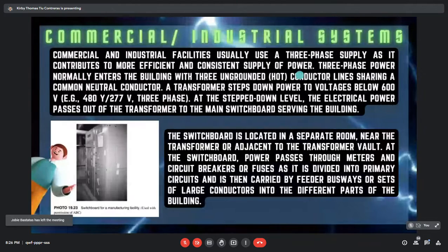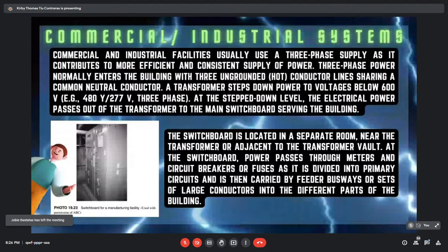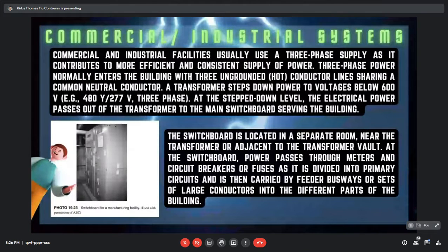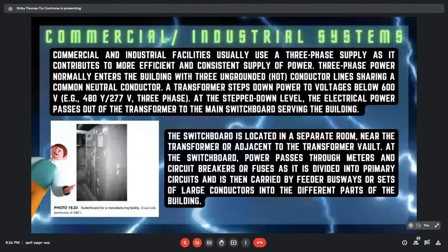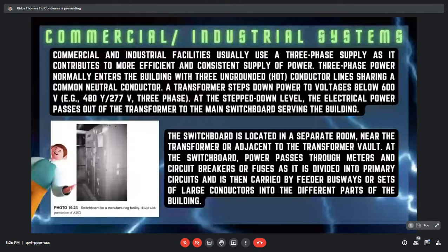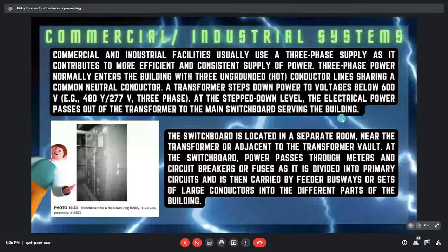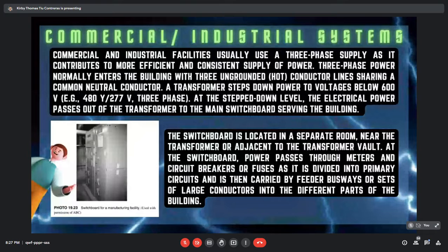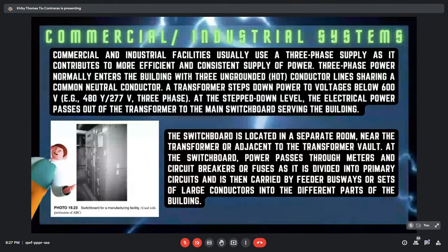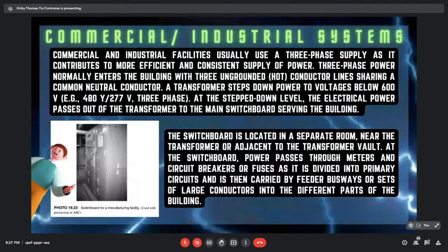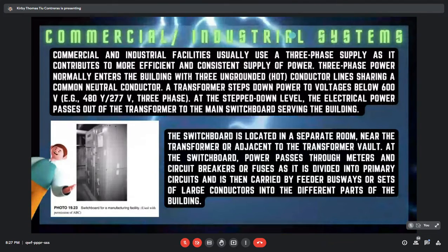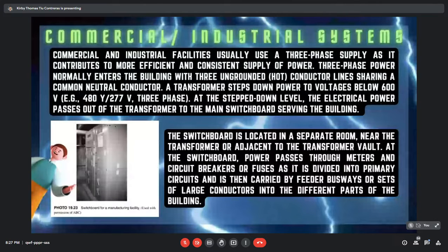Three-phase power normally enters the building with three ungrounded hot conductor lines sharing a common neutral conductor. A transformer steps down power to voltages below 600 volts at the step-down level. At the step-down level, the electrical power passes out of the transformer to the main switchboard serving the building. Example of a switchboard is in the picture on the left side. The switchboard is located in a separate room near the transformer or adjacent to the transformer vault. At the switchboard, power passes through meters and circuit breakers or fuses as it is divided into primary circuits and is then carried by feeder busways or sets of large conductors into the different parts of the building.